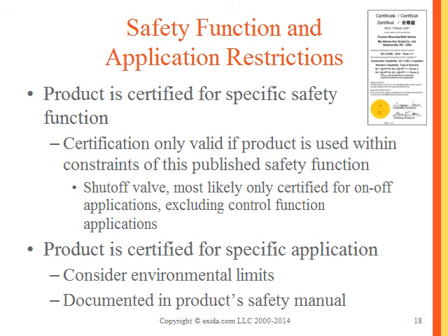So sometimes we have to deal with certain grounding requirements. You need to follow those grounding requirements before you actually can say that you are using the product within the certification that it was looked at. It's key to look at that safety manual. You need to understand how you need to use that product before you actually buy the product. So I would always urge you to talk to the manufacturer, get that safety manual before you actually purchase the product.